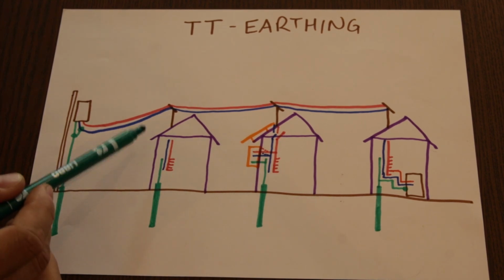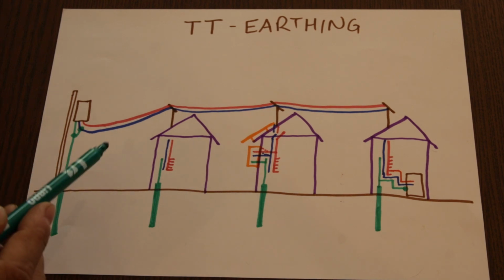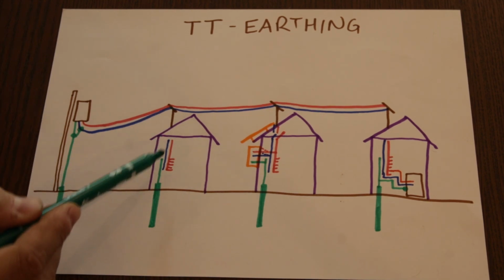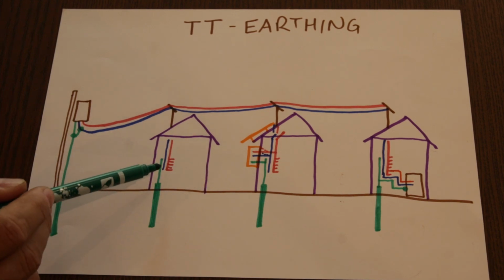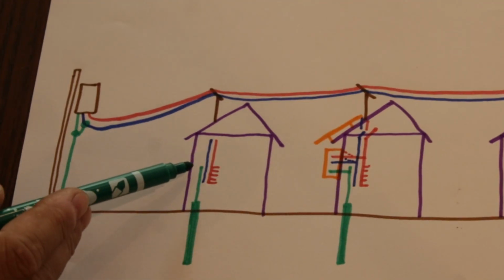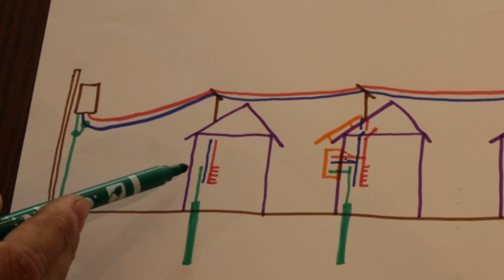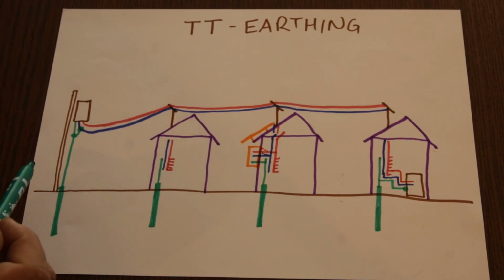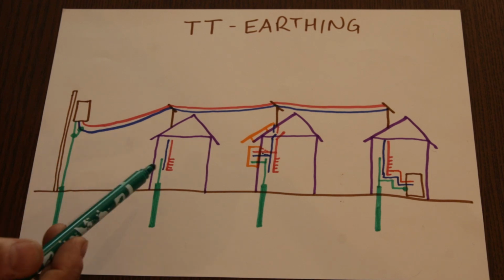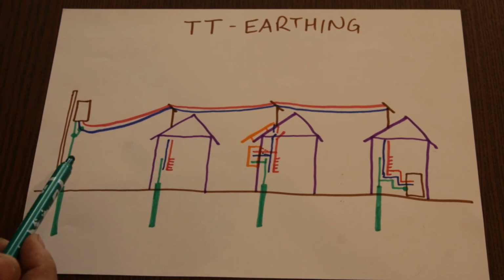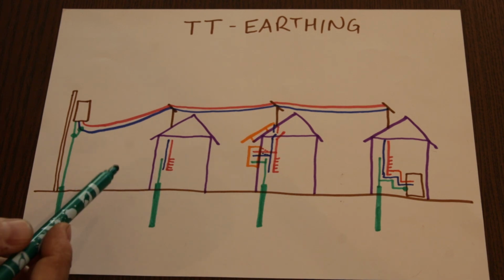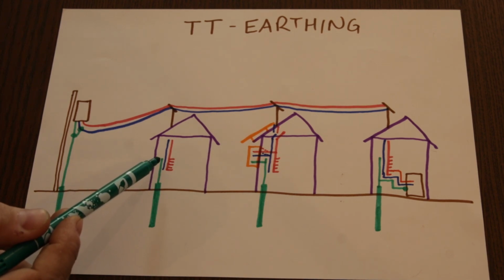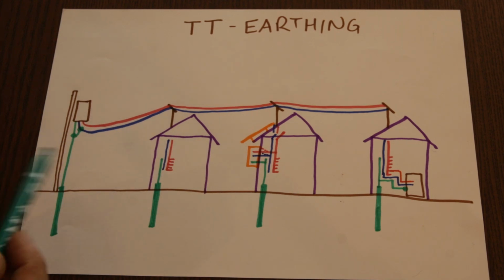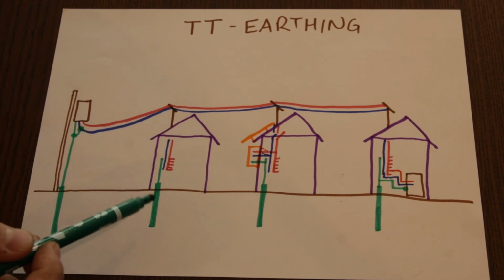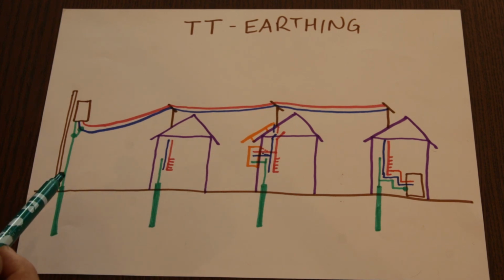When it comes to the building installation, we have again neutral and phase coming into the house. But inside the house there is no more bonding of neutral and the house earthing. So this is clearly completely separated, and in case of faults, in case of leakages in the installation, the fault currents cannot take a path back via the wire to the transformer. They have to take a path back via the grounding system of the house.